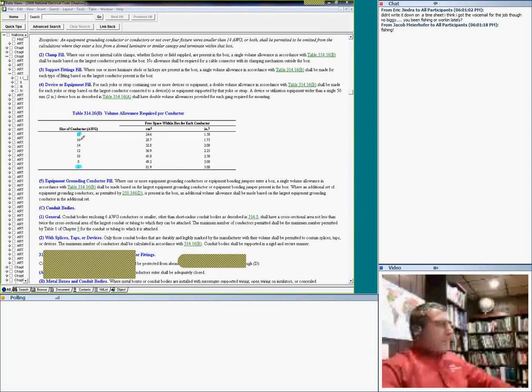Well, what if you're using the box for control, right? You can use 18 and 16 for control. For most guys, we're using these for the power, but you could be using control. Okay, using number 6, bringing it to the box, you have 5 cubic inches for number 6. Using number 12, you have to allow 2.25. You can read how they correspond to each other. So these are the most important. With 14 to 6, from 14 to 6 it goes 2, 2.25, 2.5, 3, and 5. Okay, so piece of cake, Chad.